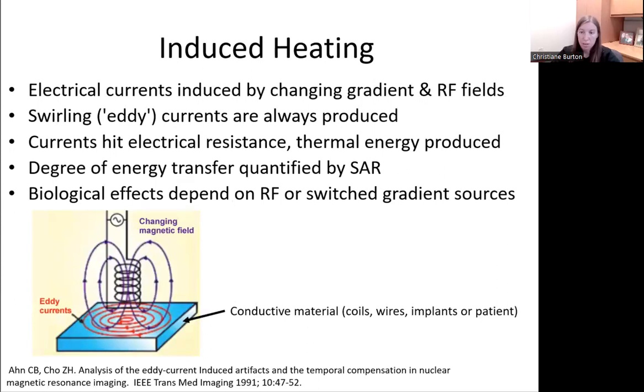Okay, so we all know that energy deposited in tissues during MRI causes tissues to heat and result in thermal injuries. But how does MRI cause thermal injury? When you have a changing magnetic field, it can generate electric eddy currents in accordance with Faraday's law of induction. When these currents encounter electrical resistance, thermal energy is produced. The conductive material in which eddy currents are induced may be metallic components of the MR scanner, such as coils, wires, or devices within or on the patient, and the patient as a whole.